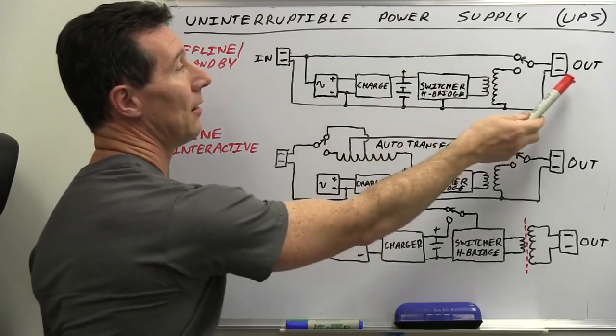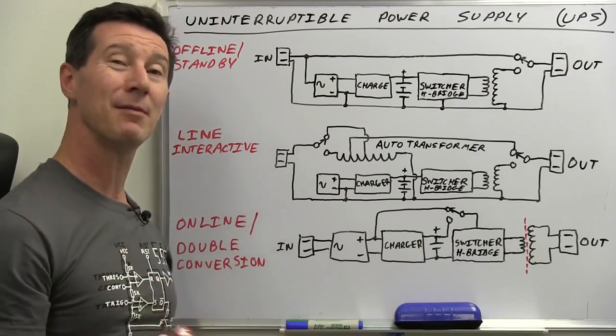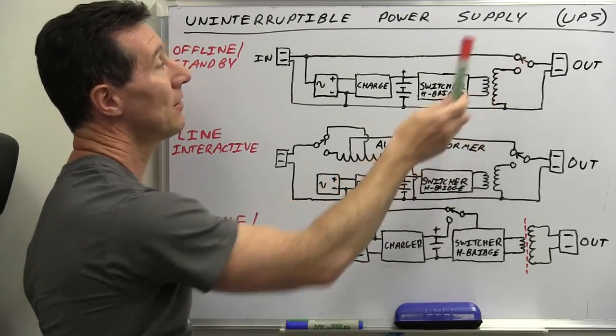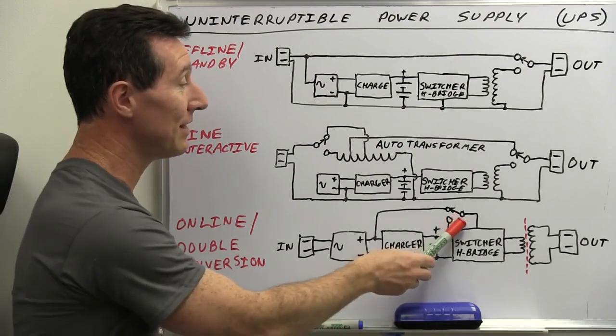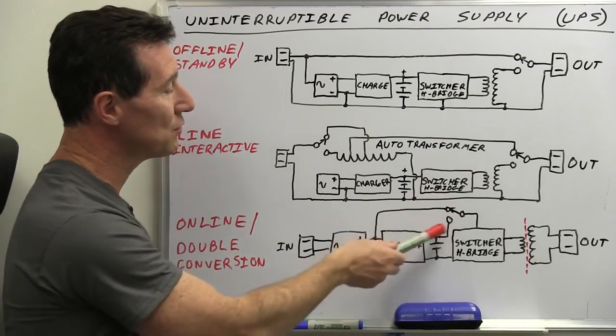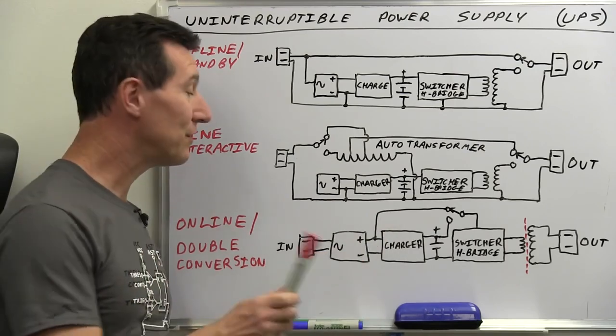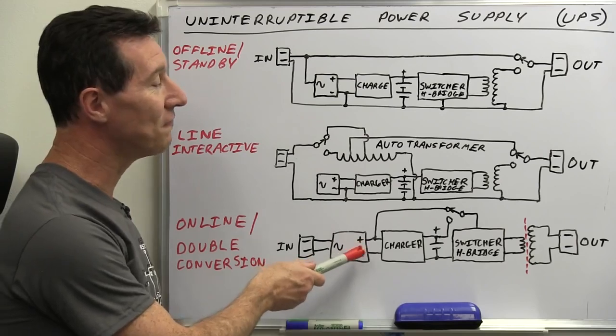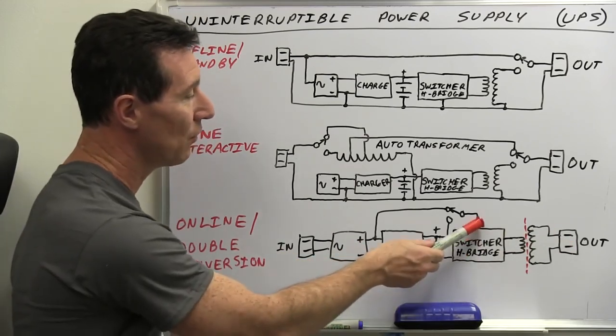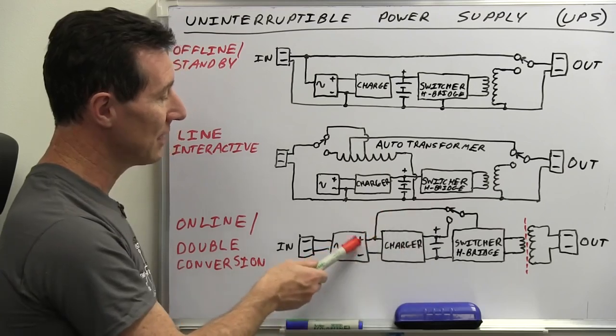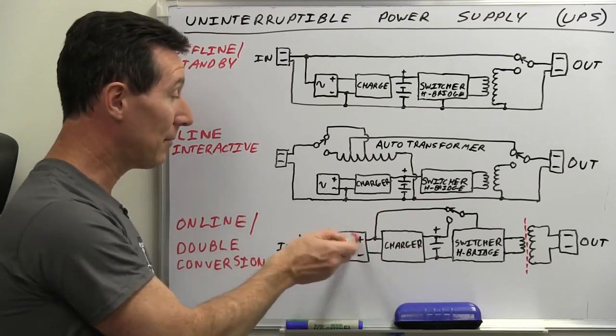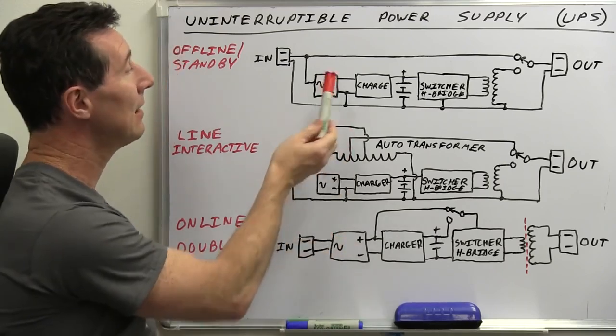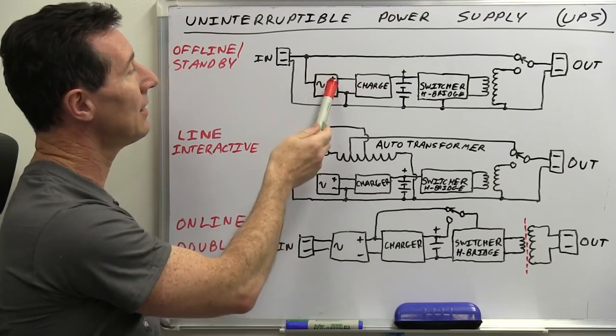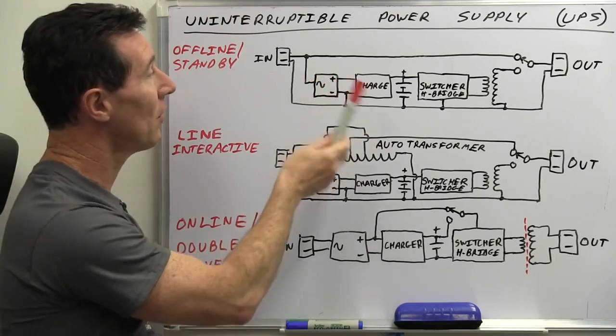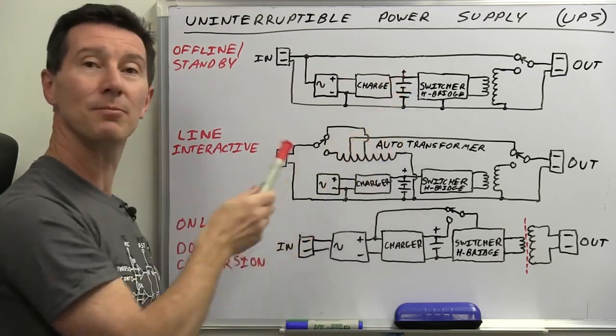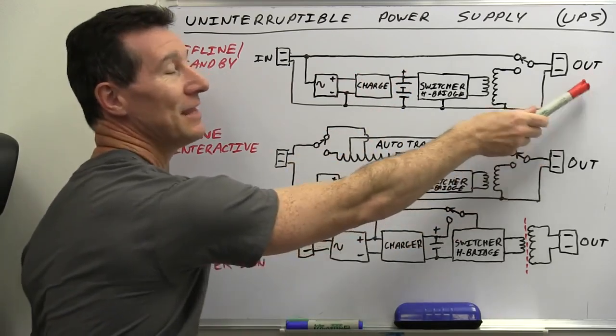Up here, if you've got, say, a typical 10 amp mains outlet, well, you only need a 10 amp relay in there. That's it. Not a problem. But down here, you need much, much higher currents. So the switching can be an issue down here. And also, this rectifier down here has to deliver the full load all the time, because you notice when it's not powered from the battery, it's got to deliver all that power from that poor little rectifier down in here, whereas here the rectifier only needs to be sized, designed well enough to deliver enough power to charge the battery, which might be much, much less than the output load is capable of.